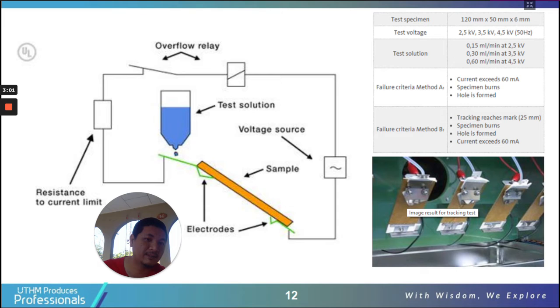So you can see here, this is the insulation sample. This is the insulation sample. This is the electrode connected to the high voltage, and this is also where we have the water droplet. Water is being supplied onto the surface of the insulation material. All right, so this is an example of the test.